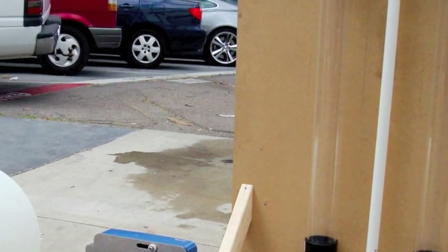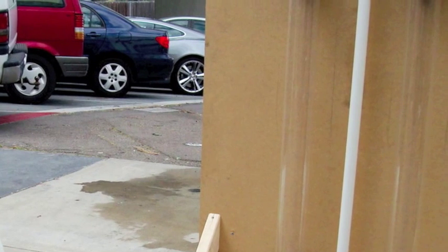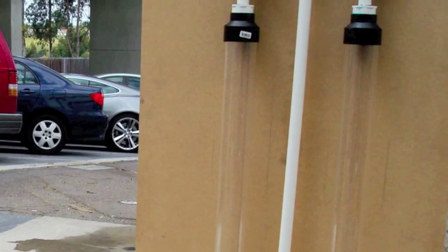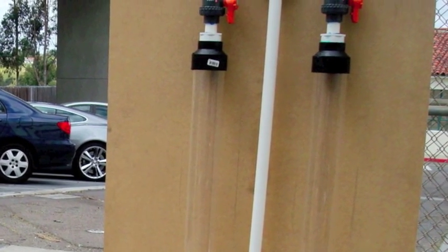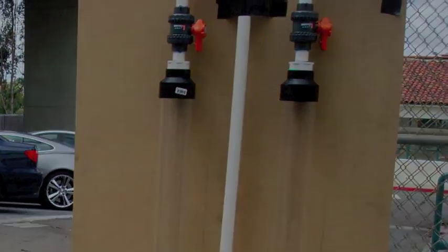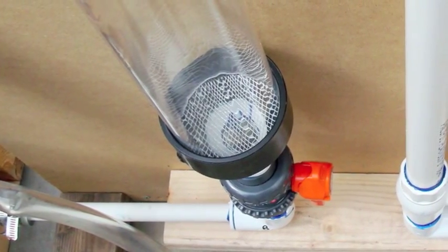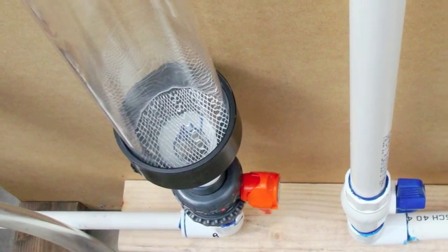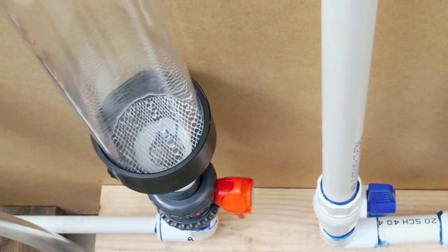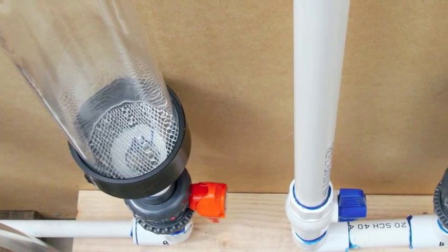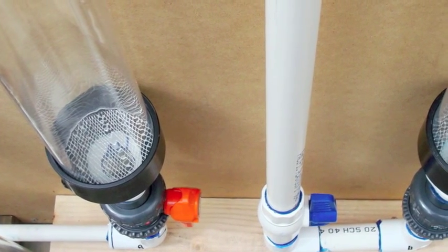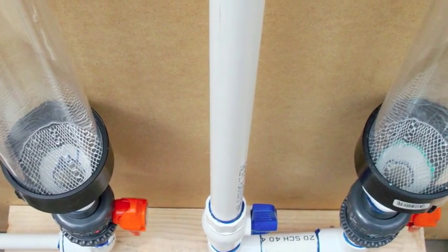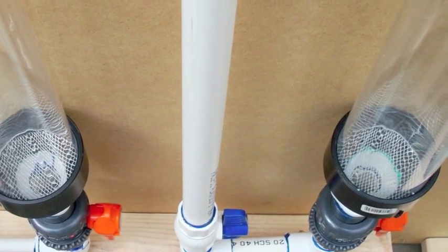Activated carbon's adsorptive properties are used to remove organics. Generally, adsorption takes place because all molecules exert forces to adhere to each other. Activated carbon adsorbs organic material because the attractive forces between the carbon surface, which is nonpolar, and the contaminant, which is also nonpolar, are stronger than the forces keeping the contaminant dissolved in water, which is polar. Activated carbon can remove and destroy residual disinfectants, chlorine and chloramine, through a catalytic reduction reaction. This is a chemical reaction that involves the transfer of electrons from the activated carbon surface to the residual disinfectant. In other words, activated carbon acts as a reducing agent.